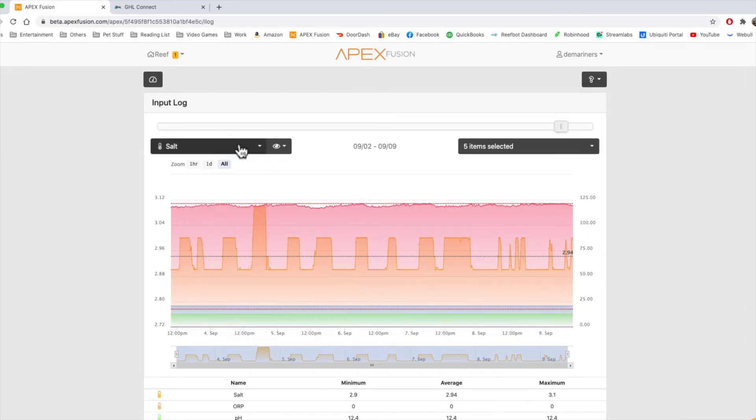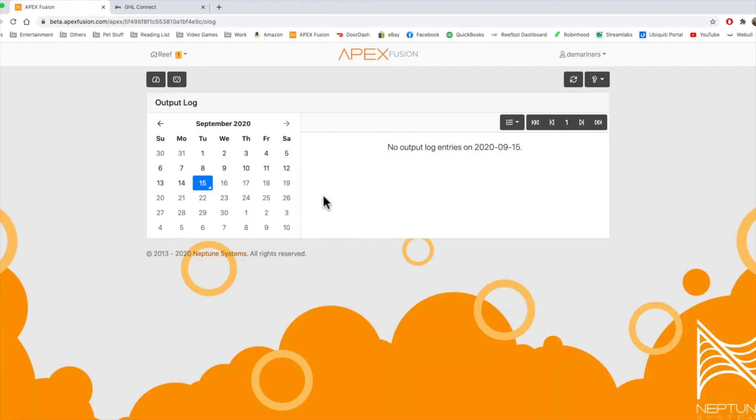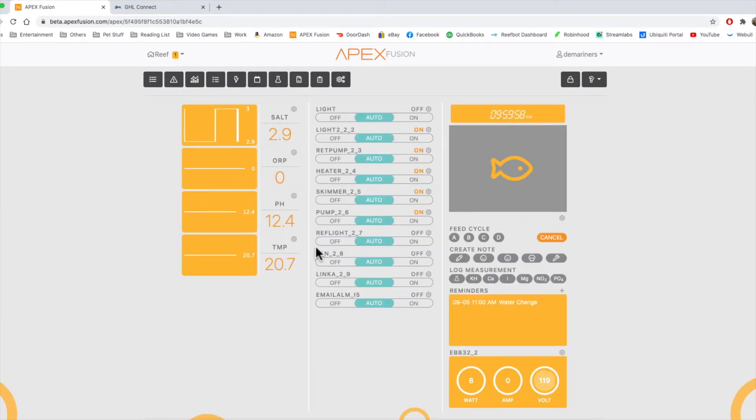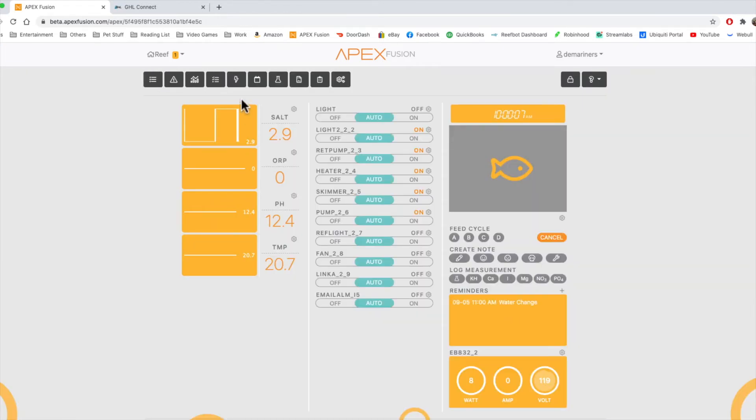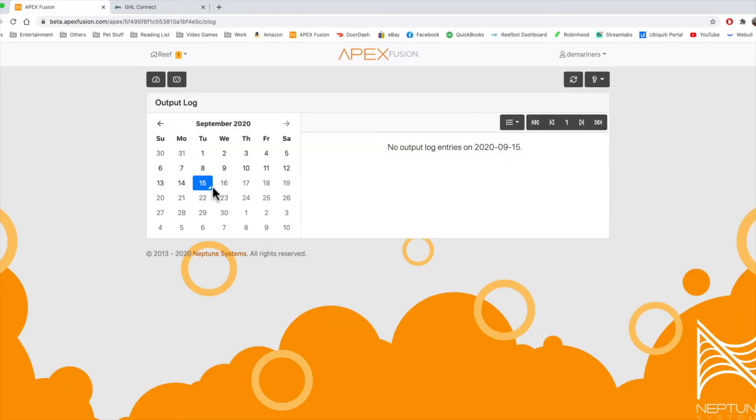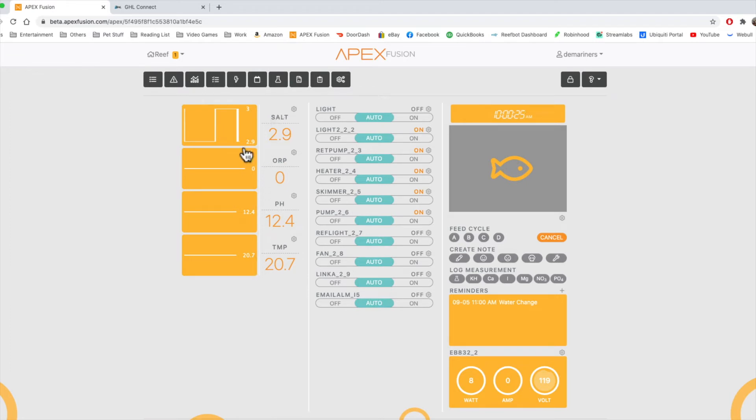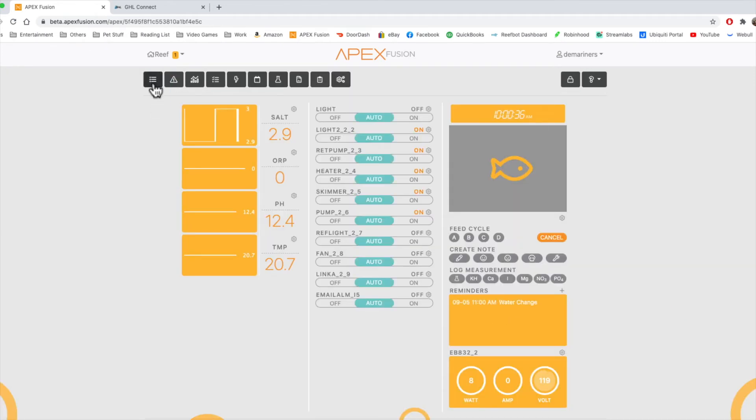If we go on to our output log, which is going to be right here, that is where we see when things have turned on and off. This will only show values if you have enabled the log. So for instance, if we want to know when our return pump was on and off, we'd have to enable the log right here. When you enable the log, it'll then start producing values in your output log. You're only going to want to select specific devices that you want to monitor maybe for testing purposes. You don't want to have it logging every single thing that you're doing, because it can again clutter and slow down the data that it's collecting. So the recommendation there is to keep that tidy and only put on specific things, maybe like your email alarm or possibly power monitoring, which we went over in the last episode.